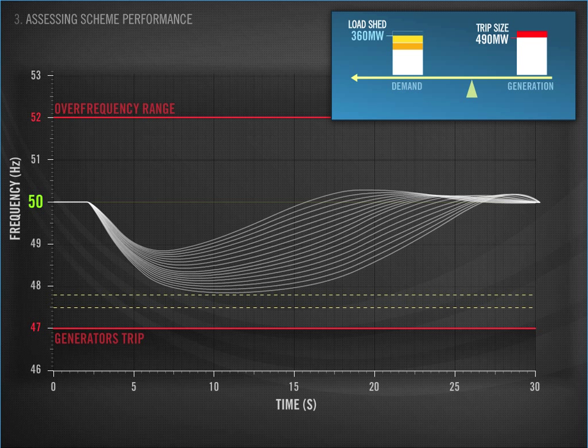The events being shown on the seesaw and graph are referred to as contingent events. To cover these events, we rely on purchasing interruptible load and generator reserves. This prevents the frequency from falling below 48 Hz and returns it to the normal range. These aren't really the events we are concerned about with UFLS.